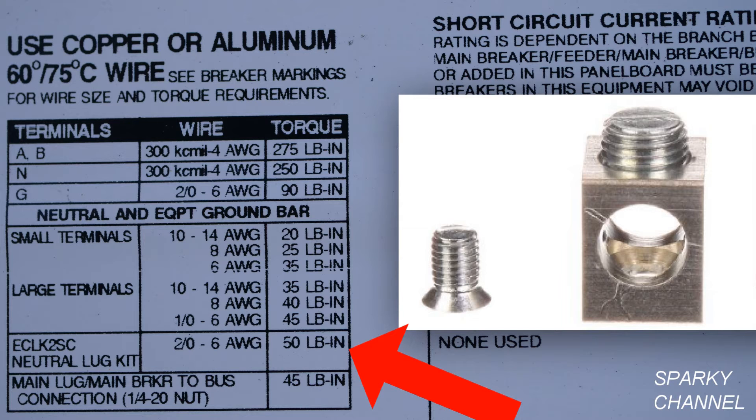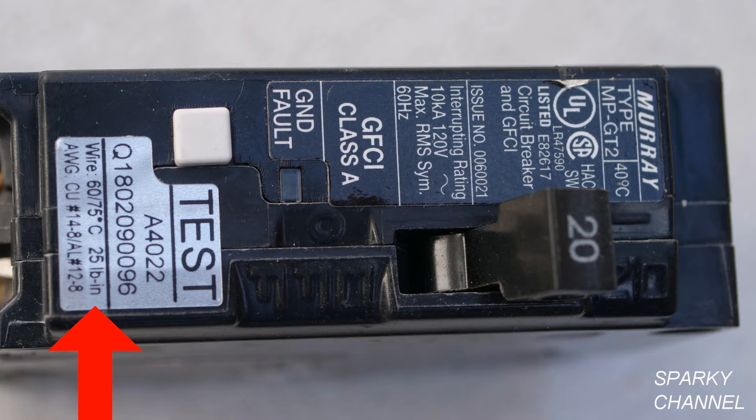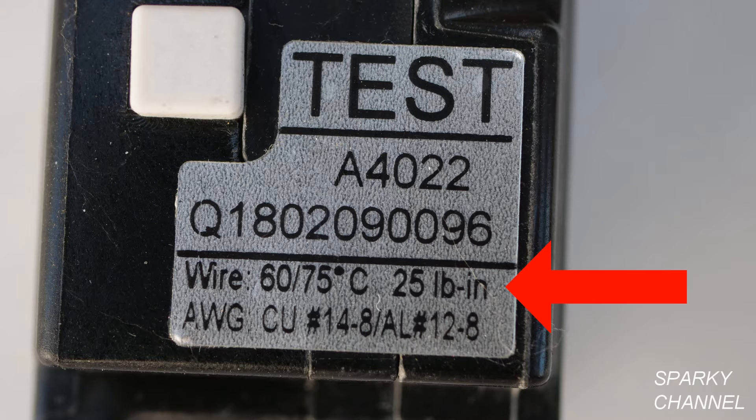The neutral lug kit seen on the right would be torqued at 50 pound-inches. The quarter-inch nuts that the red arrows are pointing to are to be torqued at 45 pound-inches. The torque rating for breakers will be found right on the breaker — this one is 25 pound-inches.